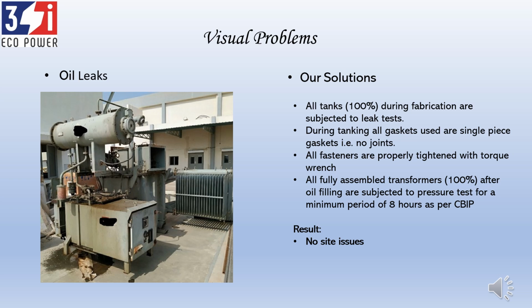At the tank fabrication stage, we buy tanks from our own subsidiary company, United Engineering Works. We ensure 100% leak tests during fabrication of the tanks, and everything is properly documented - all the reworks, the number of leaks during fabrication, how they're contained, the duration of the leak test, and the pressure applied during the test. All fabricated tanks are subject to 100% testing, and only after passing these tests does fabrication proceed further, such as painting.